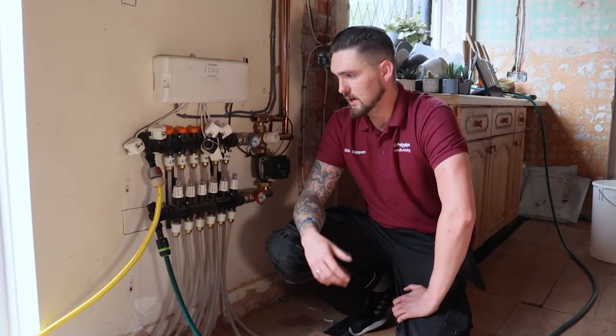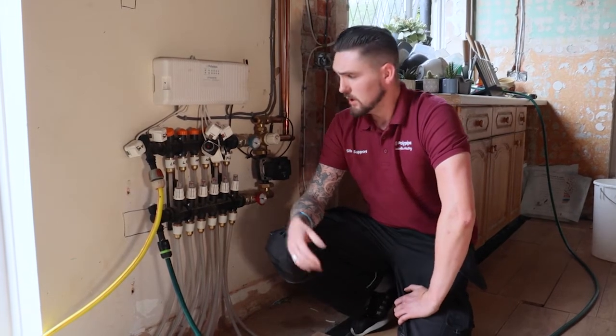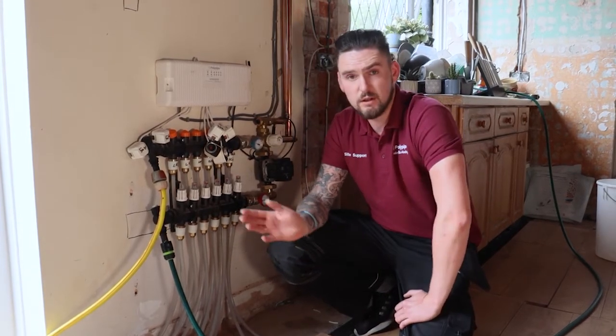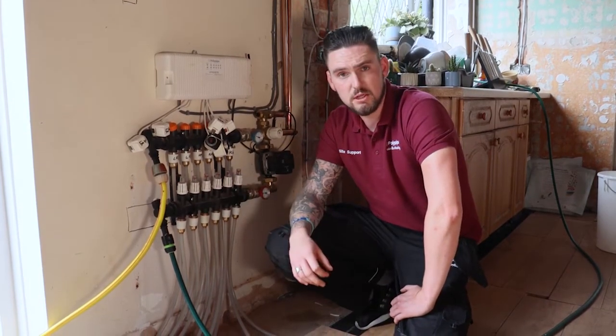Today we're looking at commissioning our polymer manifold. We're actually in a property where an overlay plus system has gone in. As you can see, we've used the polymer manifold, piped back to the boiler set up as an S plan. We're looking to fill the system first, circuit by circuit, bleeding all the air out, and then we're going to do a heat commission after that.